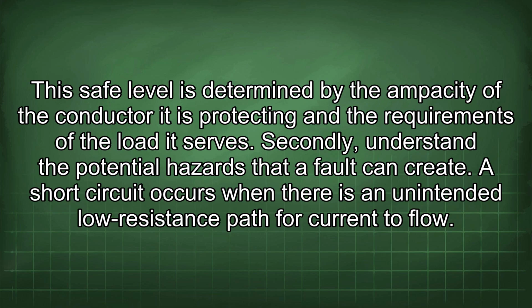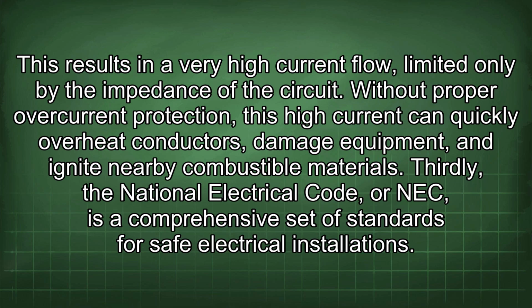A short circuit occurs when there is an unintended low resistance path for current to flow. This results in a very high current flow, limited only by the impedance of the circuit. Without proper overcurrent protection, this high current can quickly overheat conductors, damage equipment, and ignite nearby combustible materials.